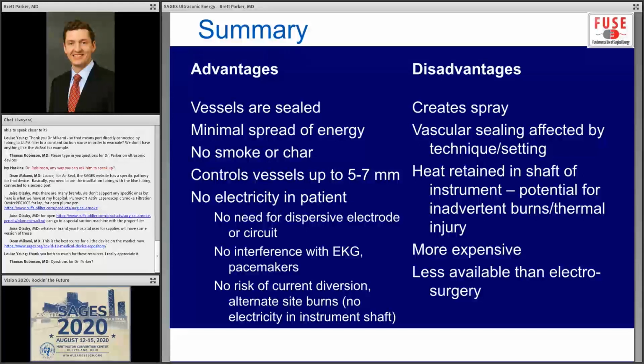There is no electricity inside of the patient, so there's no electrical circuit to consider. There's no dispersive electrode or capacitive coupling or insulation failures that you need to consider, and this will be highlighted further in the next talk when we talk about patients with cardiac implantable devices, which is a great advantage of the ultrasonic surgical shears.